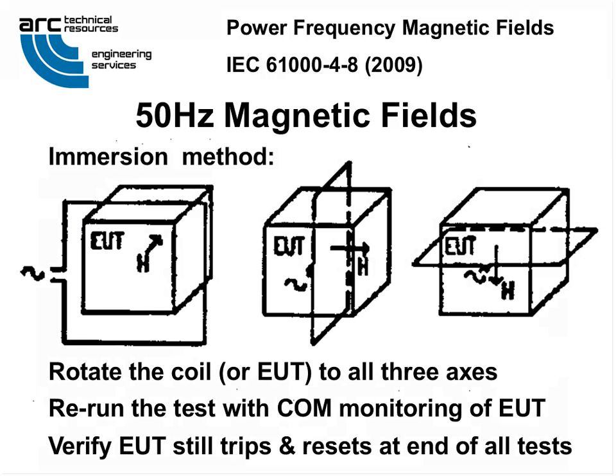These power frequency magnetic field tests are all run by the immersion method. It requires that you rotate the coil or the EUT to all 3 axes, and you rerun the test with a COM port monitoring the EUT's acceptance on each axis if it has a COM port. And this has been written for communications networking equipment, so it probably has a COM port. Later on next year, when this standard is extended to everything utilities buy, including stuff that doesn't have a COM port, you're going to actually have to look at the product and determine if it's operating normally or if it's doing what its critical functions are. And you need to verify that the EUT still either trips and resets if it's a relay or has its critical functions remaining intact at the end of this test.